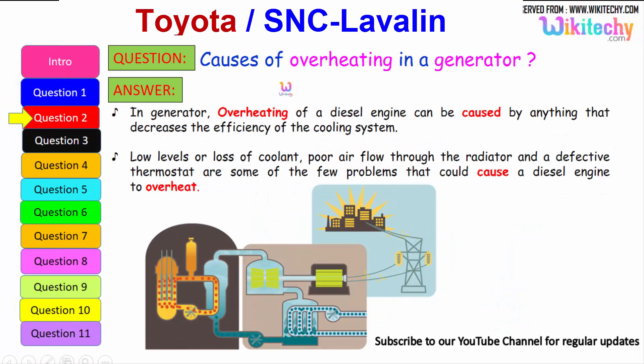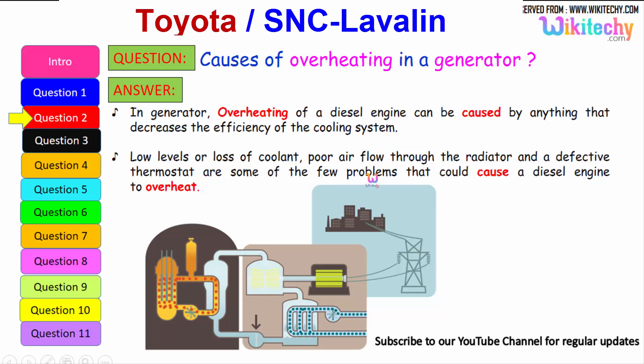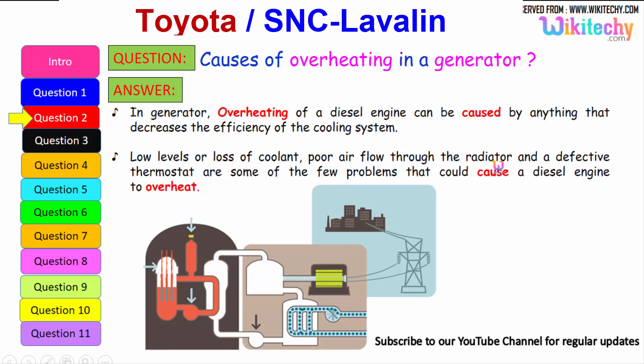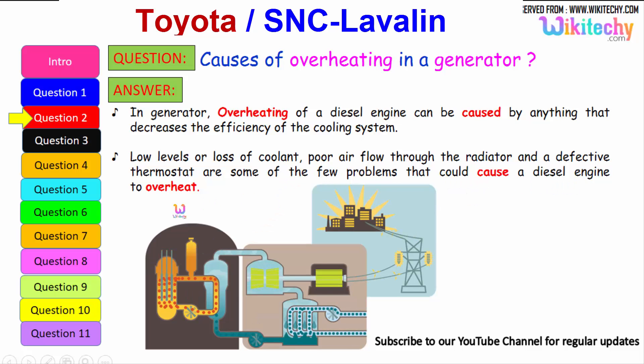Let us move on to the next question: causes of overheating in a generator. Overheating of a diesel engine can be caused by anything that decreases the efficiency of the cooling system. It can be due to loss of coolant or low levels of coolant, poor air flow through the radiators, or a defective thermostat — these are some of the problems that could cause a diesel engine or generator to overheat.